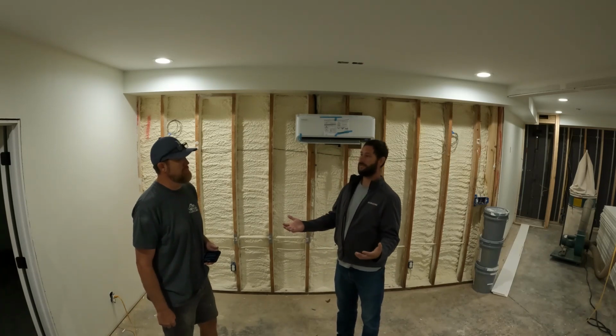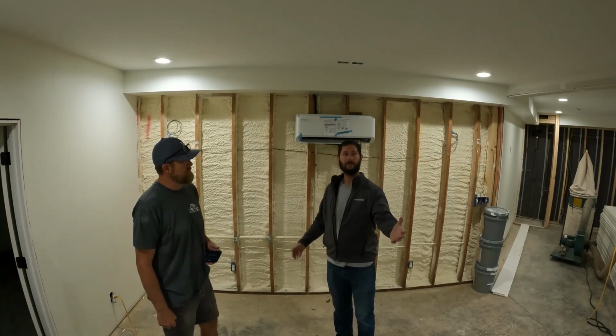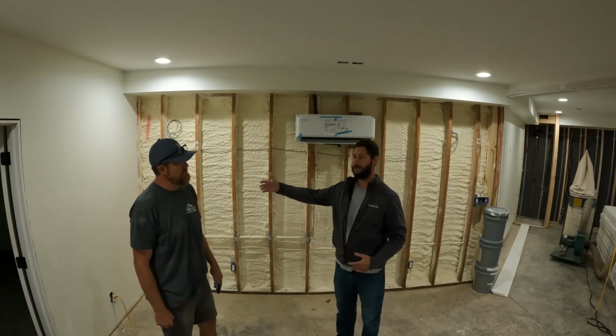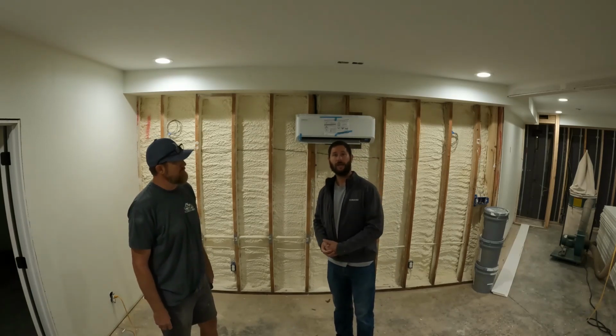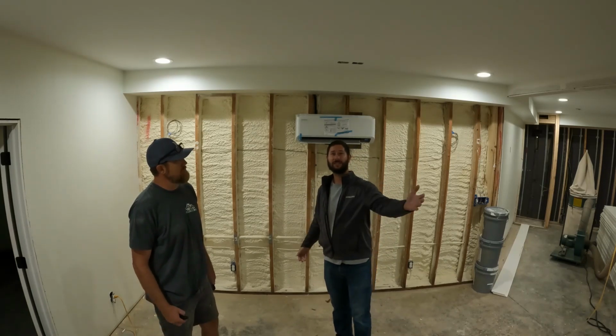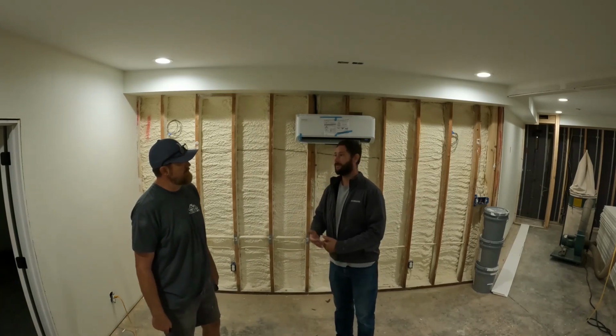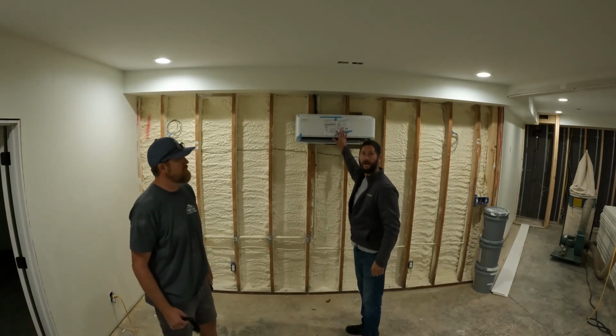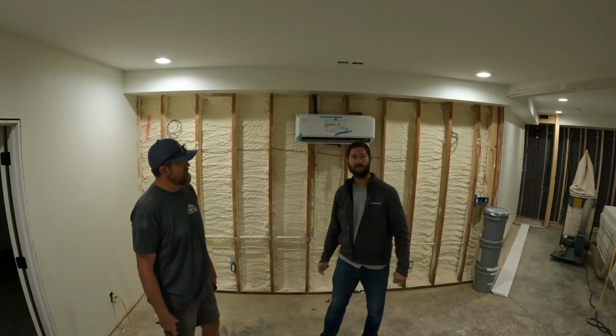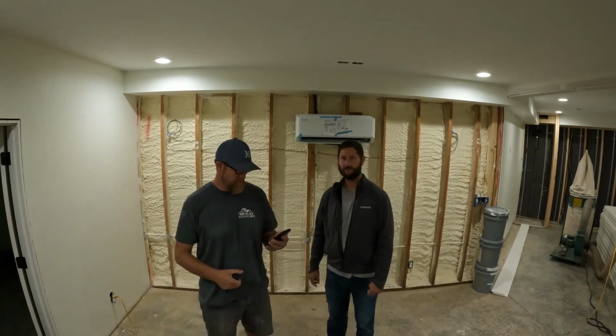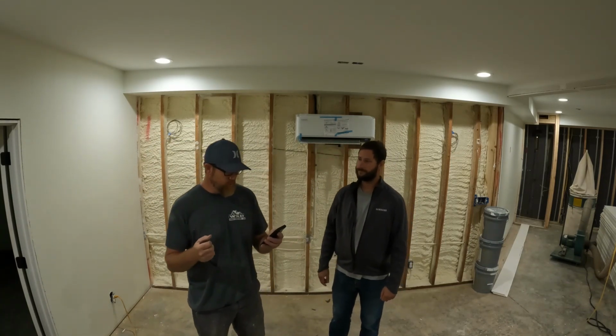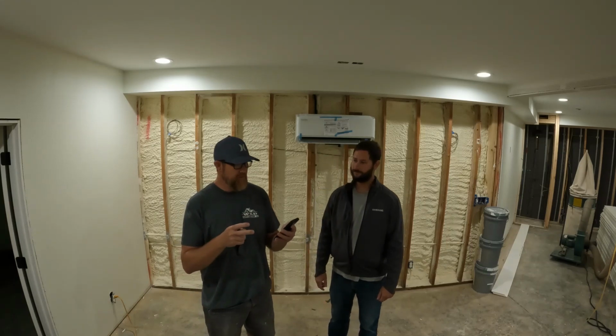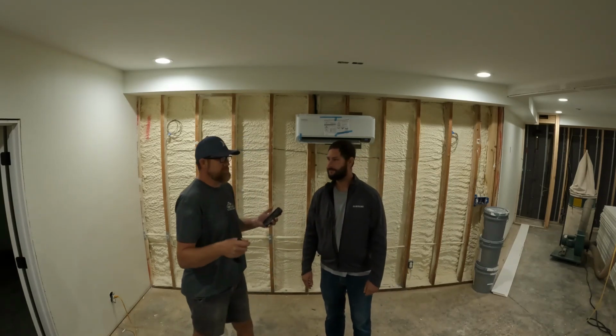But with our commercial systems where you have upwards of 48 indoor heads and you have 10, 20, 30, 40 ton outdoor units, you can actually run line set lengths over 600-700 feet. But that's for commercial. But this residential, 98 feet is the furthest length that we can use. Okay, cool, dude. How do you size what ton unit and the heads that you need per square footage or whatever?